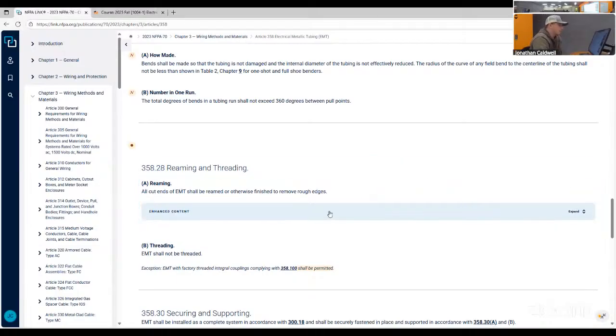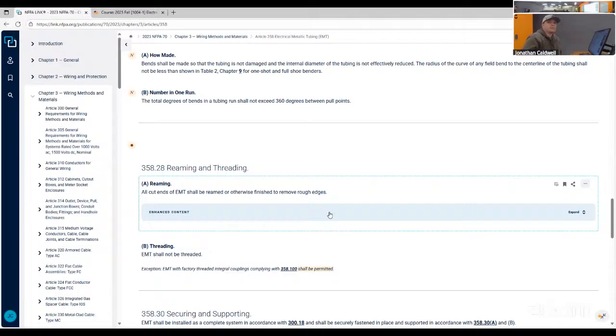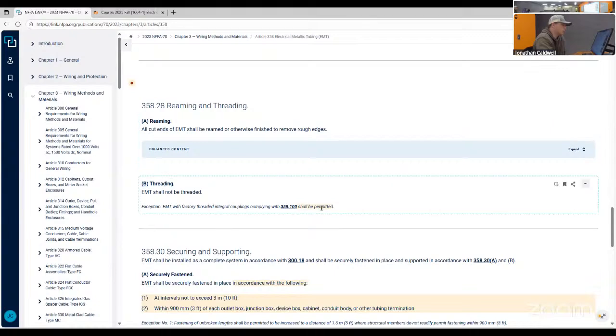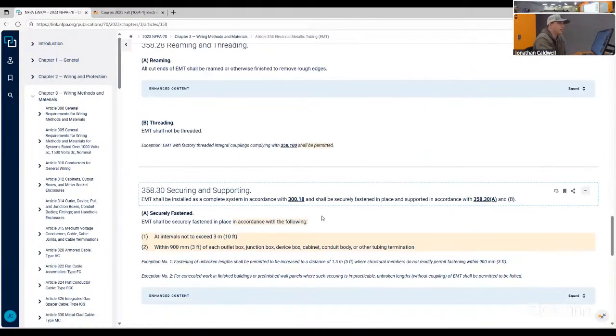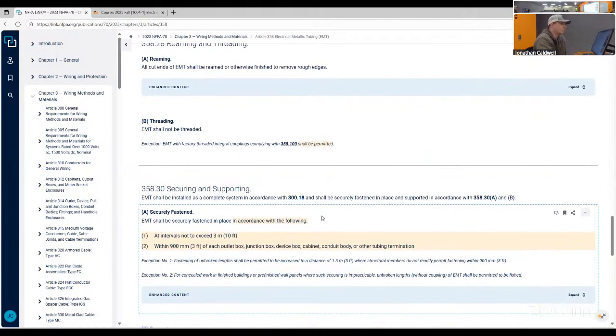Anyone that's ever worked with EMT, if you have a hand bender that likes to kink things, stop using that hand bender or get it fixed or something. Also, when you are bending, just make sure you're not getting the internal diameter ruined. It goes for all conduit, but EMT especially, it can happen and you can't notice it until you go to pull.